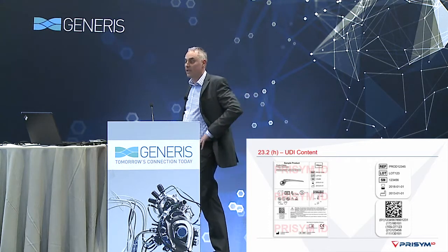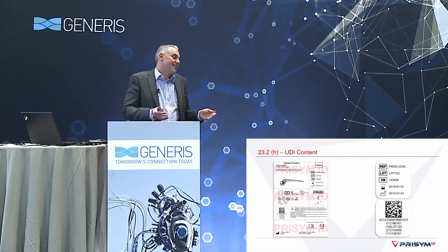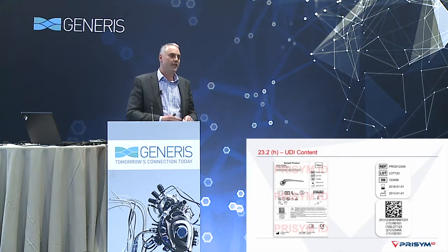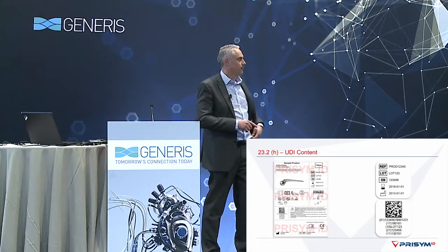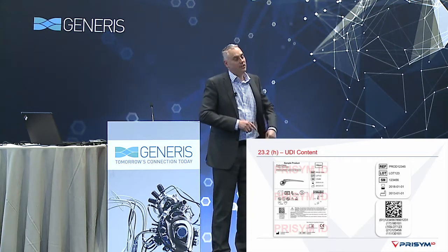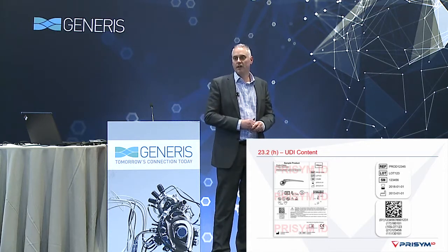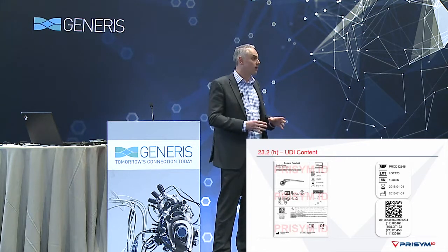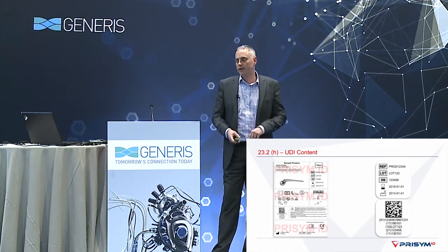Secondly, it can be a lot smaller. It can take up a lot less space on the label, and that means it's often less likely to be damaged. One thing we've seen from organizations adopting 2D barcodes with UDI is you've got to really make sure that your output, your printing of 2D barcodes, is sound, so your quality is there and it is a good 2D barcode. So barcode quality has become a lot more important, but the jump to 2D barcodes, we've seen a lot of organizations really benefit.